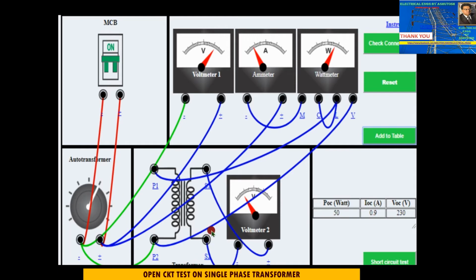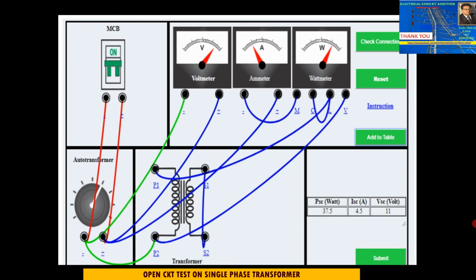So this is our single phase transformer, and this is another voltmeter V2, which is to be connected across this secondary. If you are conducting open circuit test, this secondary winding is to be kept open, so you can connect a voltmeter across this. And in the next diagram, you can see the short circuit test. Here you can see the same supply MCB is there, auto transformer is there, voltmeter, ammeter, wattmeter. These all instruments are connected at primary side.